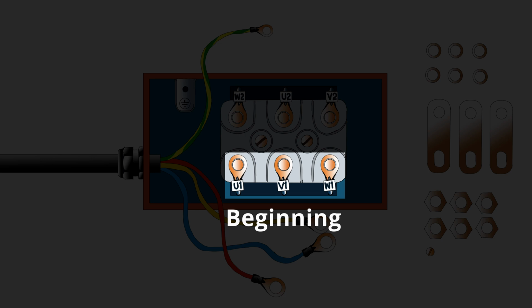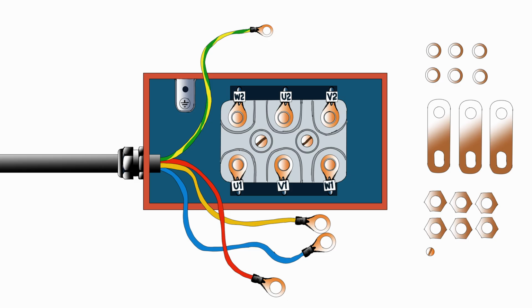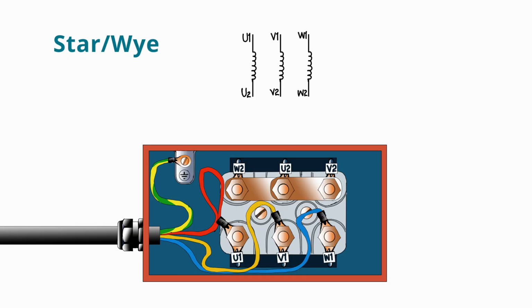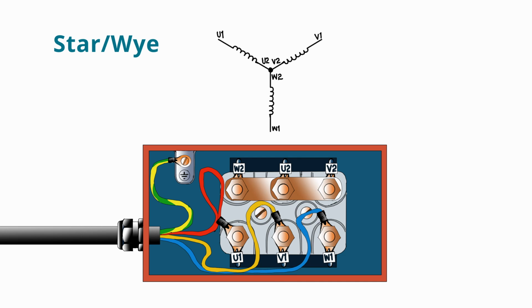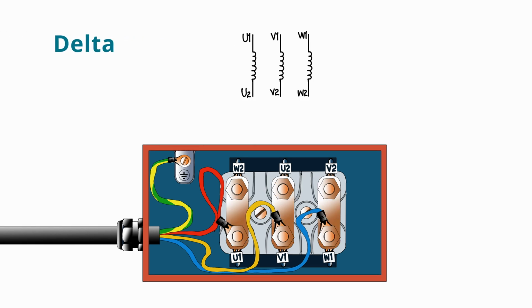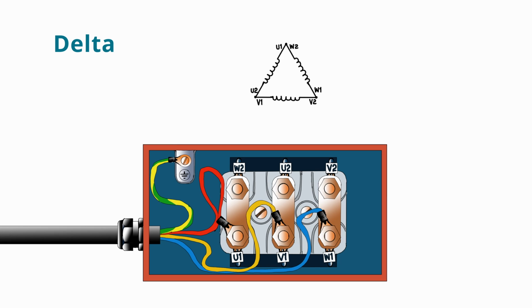Each of the three windings of an induction motor has a beginning and an end. Most manufacturers label windings using U, V, and W, with the beginnings labeled U1, V1, and W1, and the ends labeled U2, V2, and W2. To achieve a star connection, join one end of all three windings together. Then connect the 3-phase supply to the remaining 3 ends. A delta connection is achieved by connecting all 3 windings in a loop, where the end of each winding connects to the beginning of the next, forming a triangle. However, the triangle is for representation only. You can figure out your delta loop by first making sure each winding beginning is linked to the end of the next winding. Then translate those connections onto the terminals. The 3-phase supply is then connected to all the 3 points of the conjoined windings.